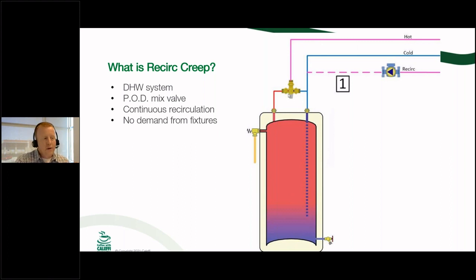And the entire reason behind recirc creep actually happening, to where that distribution system and the recirc line can come up to an incredibly high temperature, is the fact that the mixing valve is not going to be capable of completely shutting off one side or the other. Okay, now I'm going to say it right here and right now that ASSE 1017 does not require you to have the ability to completely shut off the hot or cold inlets. This is very different from your ASSE 1070 mixing valves, which are going to be your point of use mixing valves. Those do have the ability to completely shut off the hot inlet in the event of a cold water failure, but 1017, that's not a requirement.